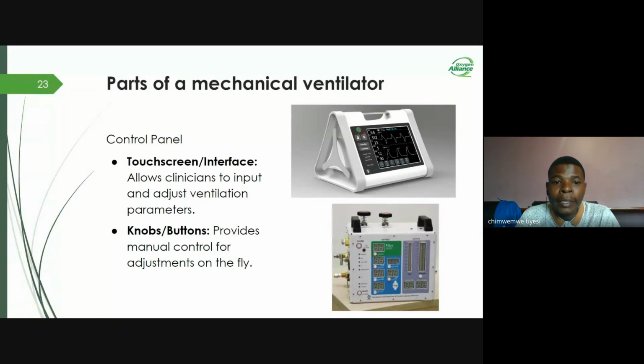Some ventilators have a combination of both knobs and buttons. Others just have the knobs and buttons and also the flow meters, which show the flow rate of gas and also the pressure. You may have a pressure gauge somewhere. In addition to the touchscreen interface, as I said, some ventilators are equipped with physical knobs and buttons that offer manual control options. These elements provide clinicians or nurses with the flexibility to make real-time adjustments easily, which allows quick and precise fine-tuning of ventilation parameters whenever it is needed.